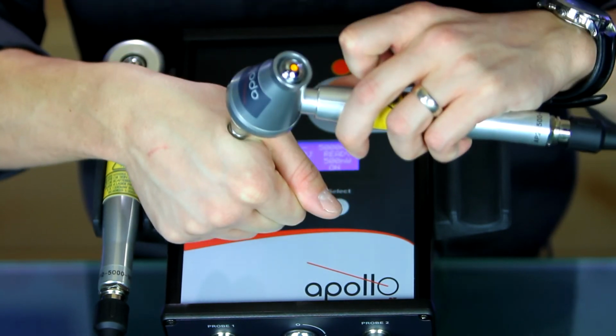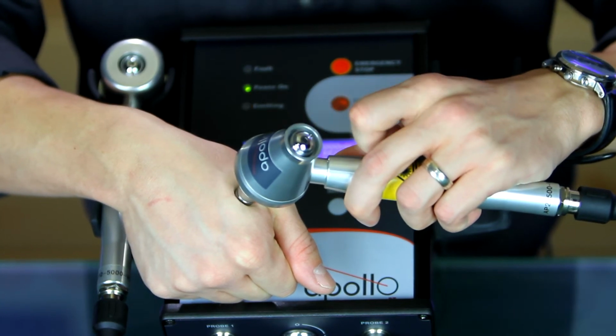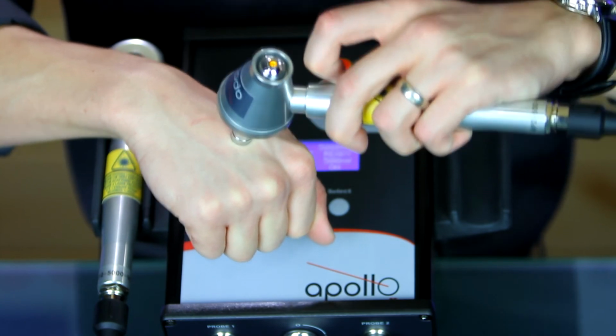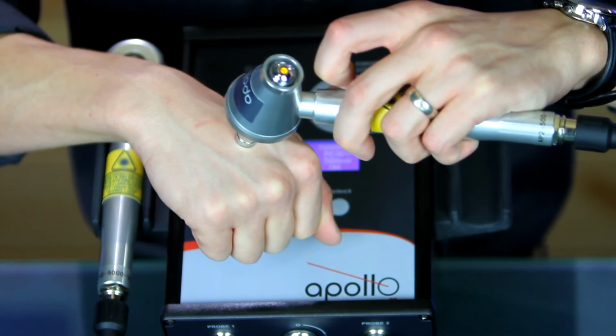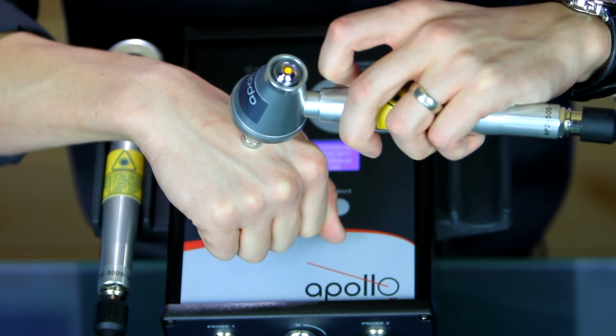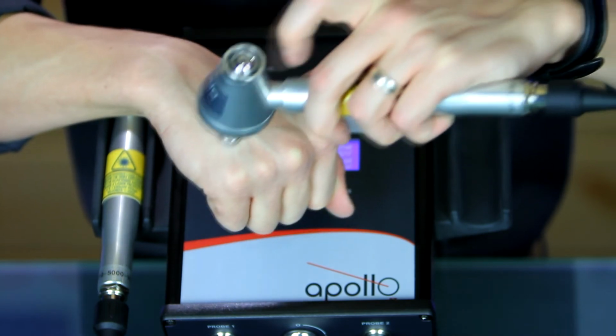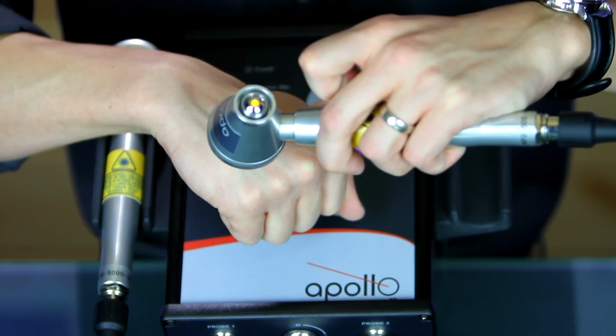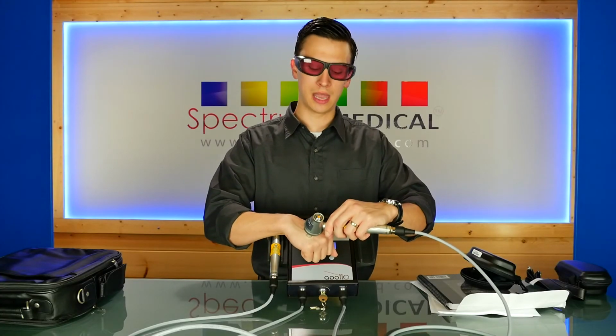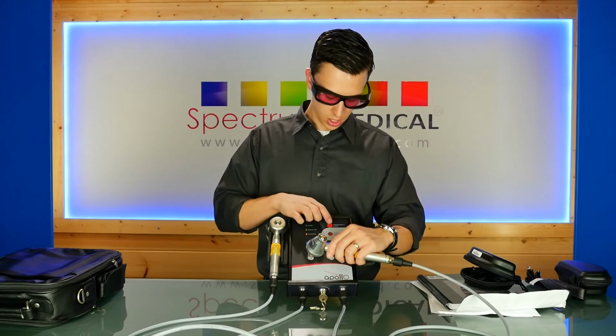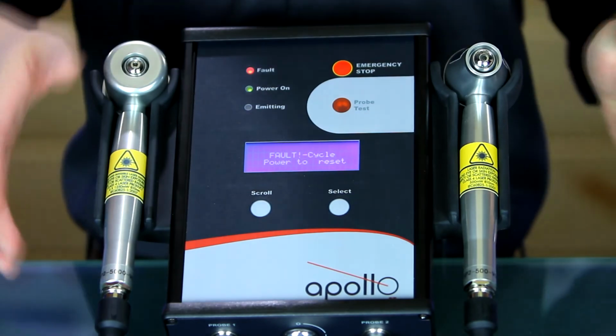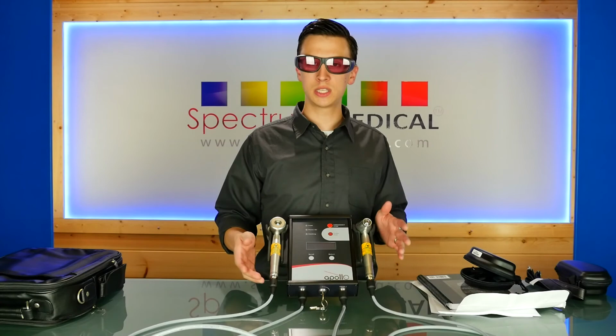If we wanted to pause a treatment, we can do so by pressing that button on the top of the probe. It's going to pause the time so that we're able to move. So maybe I want to do 10 seconds per point, but I have it set for a full minute. So I can do a few 10 seconds here, pause, move again, and then resume. Now, if at any time anything happens and you want to stop treatment totally, you can press the emergency stop button right here, and it's going to stop everything. And then it's going to alert you that you need to turn the unit off and allow it to reset before you can turn it back on and begin treating again.